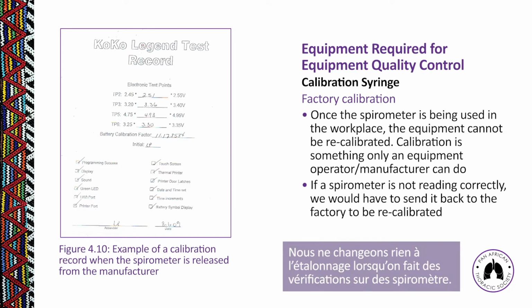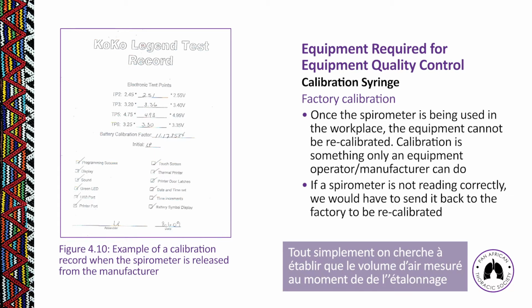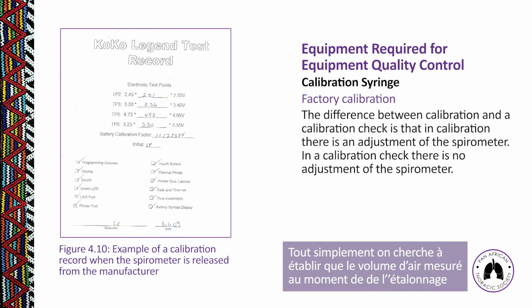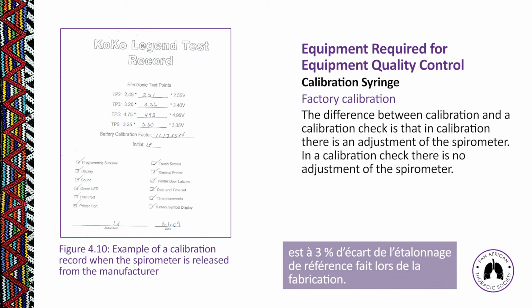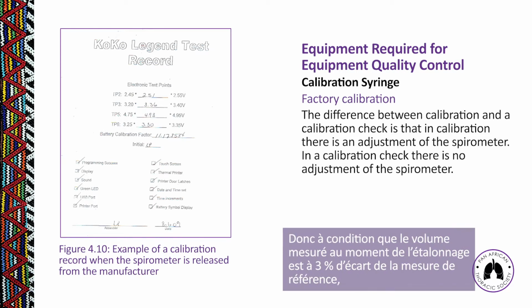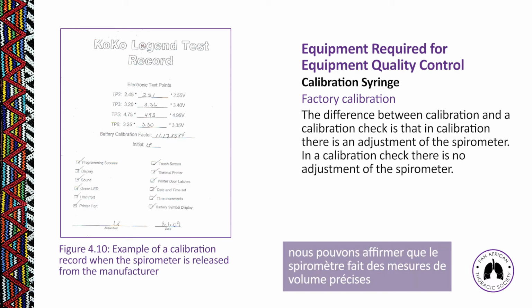So every time we do a calibration check, we're not resetting anything in our spirometer. All we're doing is checking that the volume of air measured at the time of the calibration is within 3% of that baseline factory calibration. So as long as the volume measured at the time of calibration is within 3% of the baseline calibration, we can say that the spirometer is reading volume accurately.